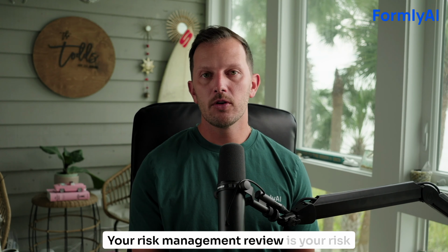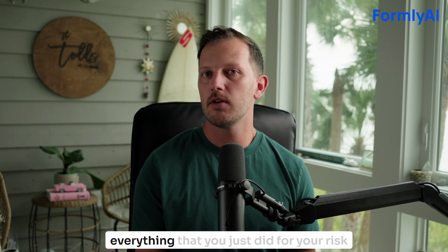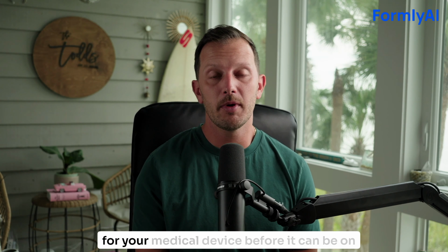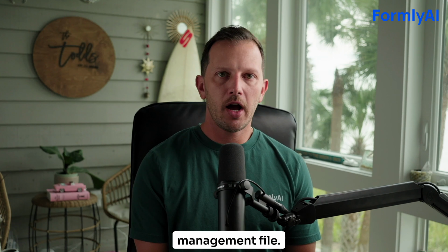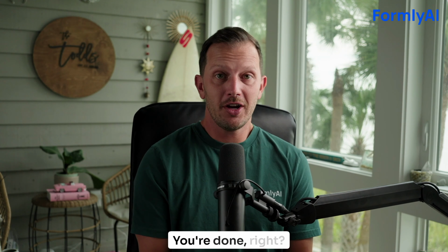Now let's talk about risk management review and what happens in the post-market. Your risk management review is your risk management report. It's essentially a report that summarizes everything that you just did for your risk management. So it's fairly simple, it's a summary, and you just have to have it for your medical device before it can be on the market. So let's say you finished your whole risk management file, you got your CE mark, your product's on the market, you're done, right?